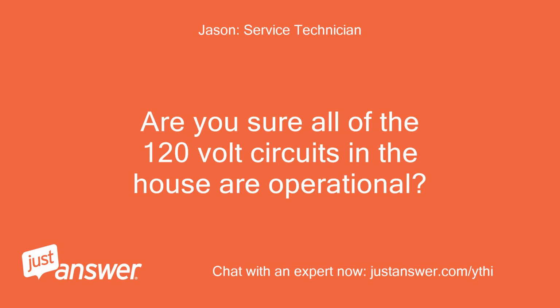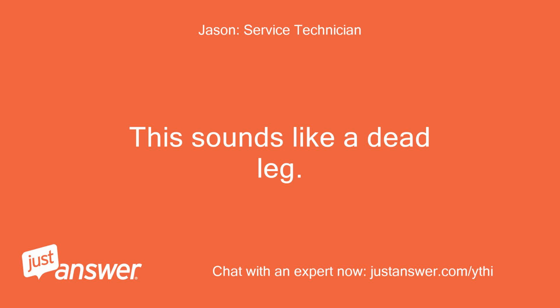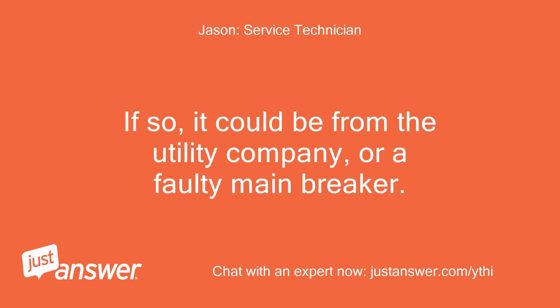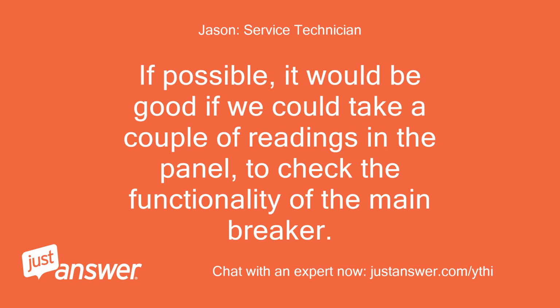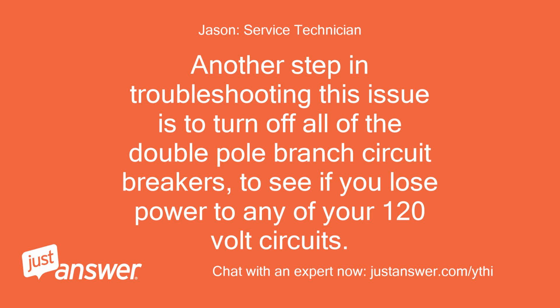Are you sure all of the 120-volt circuits in the house are operational? This sounds like a dead leg. If so, it could be from the utility company or a faulty main breaker. If possible, it would be good if we could take a couple of readings in the panel to check the functionality of the main breaker. Another step in troubleshooting this issue is to turn off all of the double pole branch circuit breakers to see if you lose power to any of your 120-volt circuits.